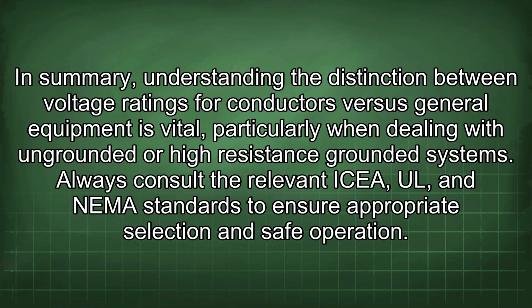In summary, understanding the distinction between voltage ratings for conductors versus general equipment is vital, particularly when dealing with ungrounded or high-resistance grounded systems. Always consult the relevant ICEA, UL, and NEMA standards to ensure appropriate selection and safe operation.